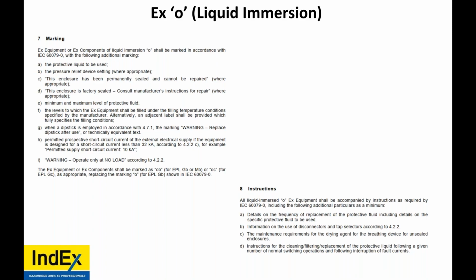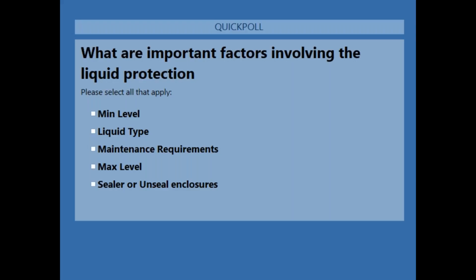Now, what are important factors involving liquid immersion? Involving the liquid, what are important considerations? The last one should say sealed or unsealed enclosures, not sealer. So remember, when we say oil filled or oil immersion, that was the old word. Now they say liquid immersion. So it can be a silicone, it can be a mineral oil, it can be an ester.